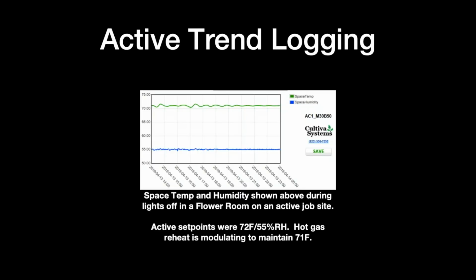This is a screenshot of an active trend log. One of the things to notice here is the blue line is your humidity. That is set at 55%, and if you look at that, it's maintaining within plus or minus 1%. Very, very tight. The green line is your temperature control. And again, the idea is to flatline those because the plants really do not adapt well to swings in temperature and humidity.